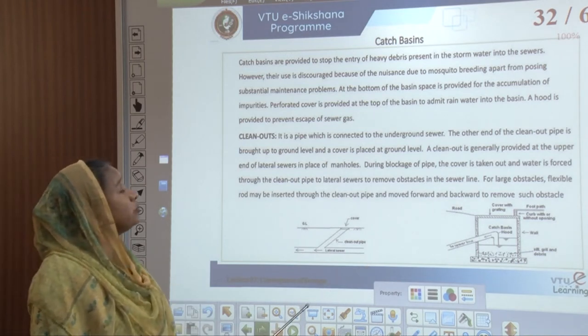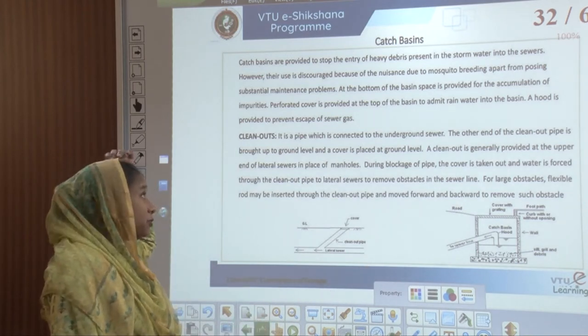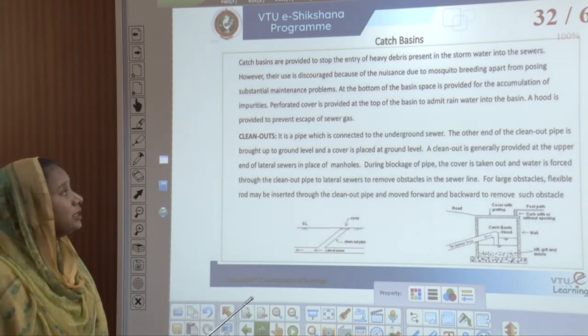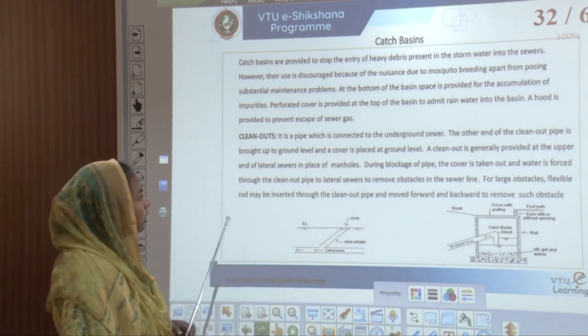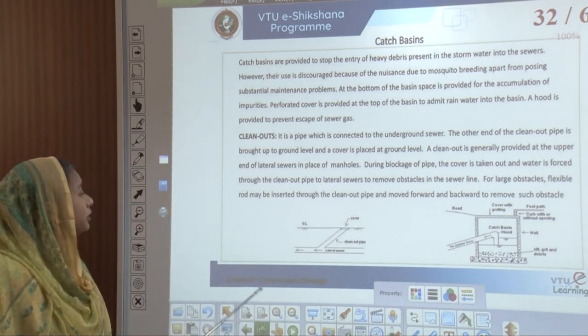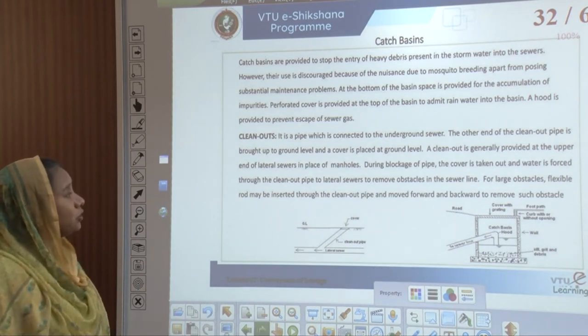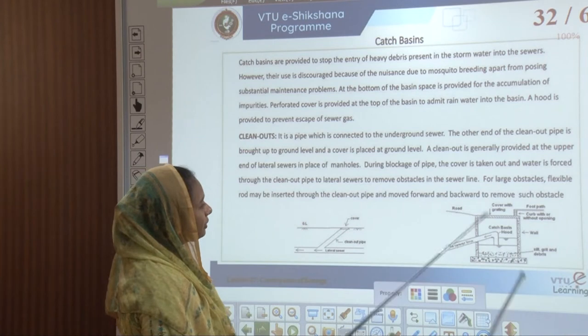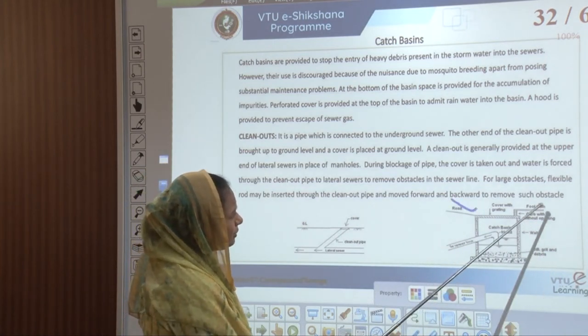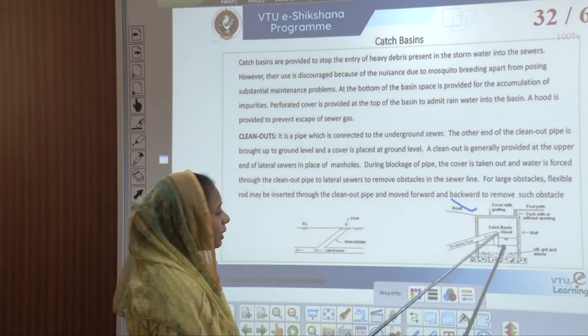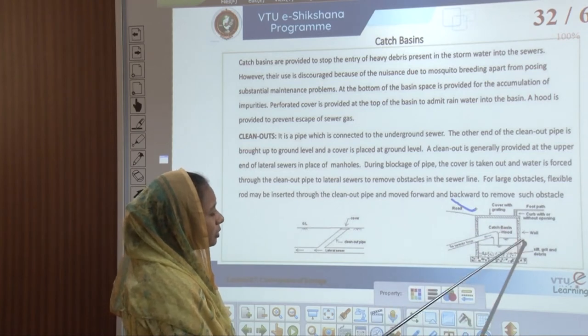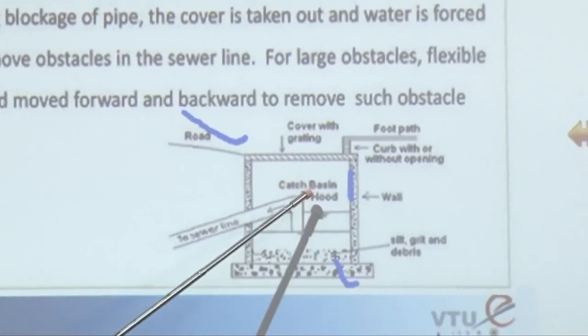Catch basins are provided to stop the entry of heavy debris present in the storm water into the sewers. However, their use is discouraged because of mosquito breeding and substantial maintenance issues. At the bottom of the basin, space is provided for accumulation of impurities, and a perforated cover is provided at the top to admit rainwater into the basin. A hood is provided to prevent escape of sewer gas. All the silt, grit and debris settle down at the base, and the water flows from the hood into the sewer line.